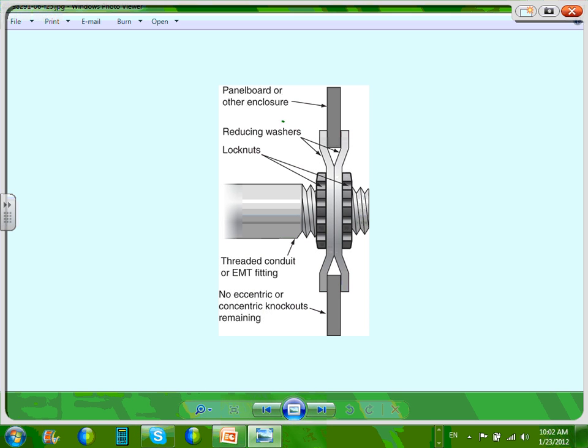If you have a reducer, anybody knows what the reducer washer is? These little things here that reduce the hole to match the conduit. Can you see that? The hole is bigger than the conduit in the box, so you have to have these reducers. When you use that, you have to have 2 lock nuts, one inside, one outside, threaded conduits or EMT fittings. So this will basically get you a good equipment grounding conductor out of this conduit, especially with the reducers.